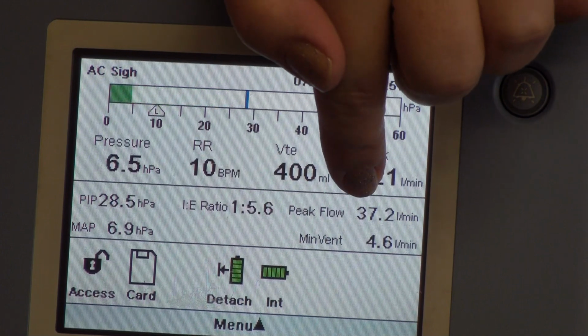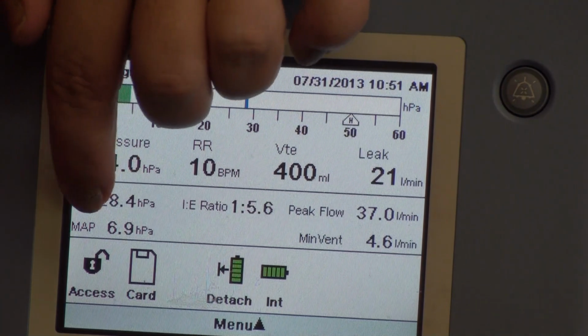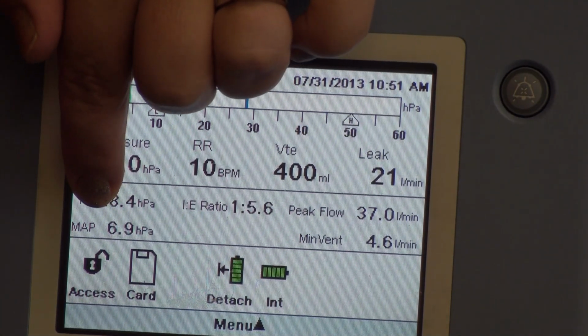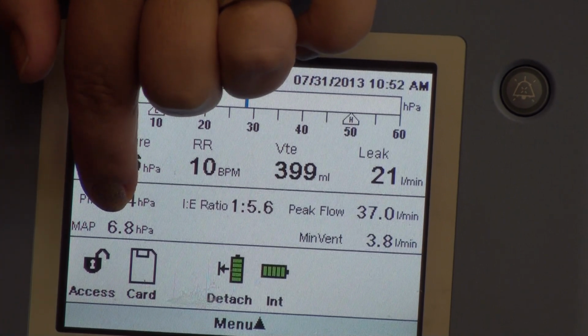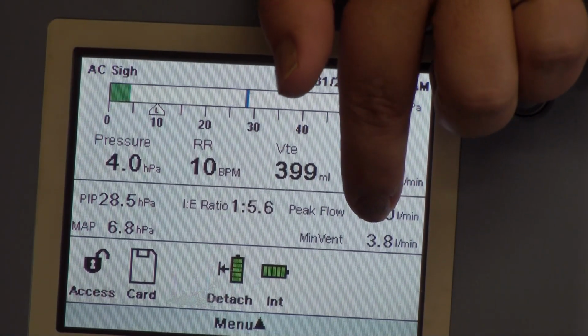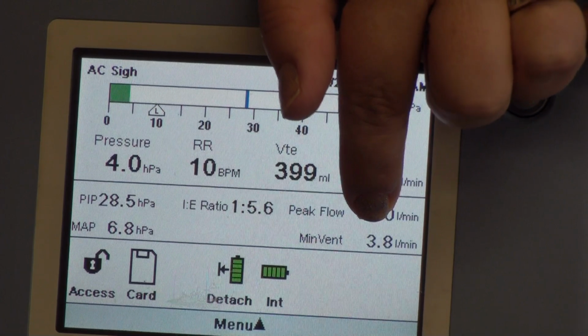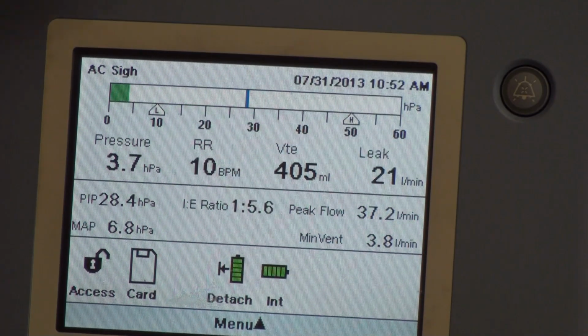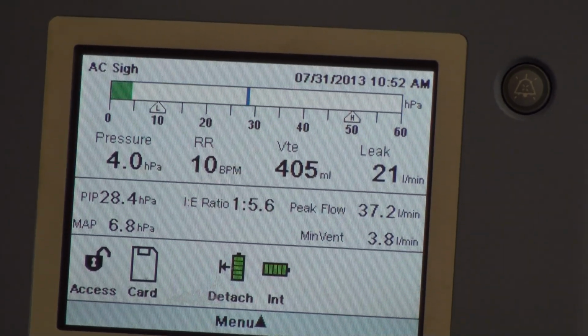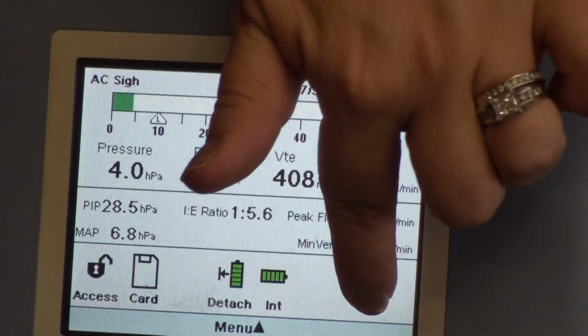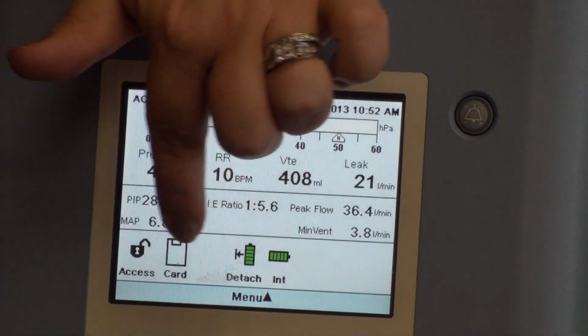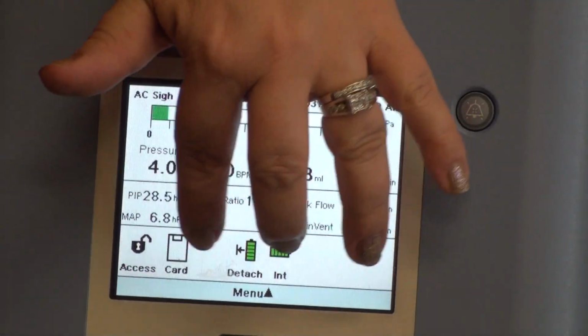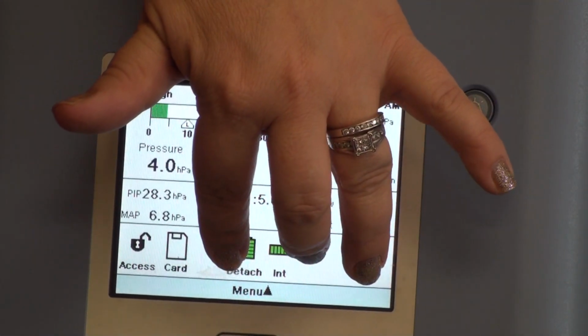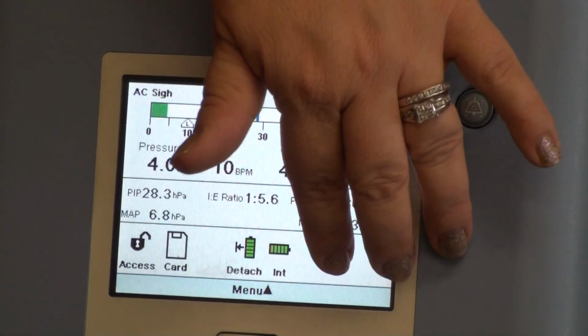I had 37.2 in that one. My mean airway pressure is down here. That's just my average of my airway pressure. And then over here, I'm going to have my minute ventilation, which right now is at 3.8. The next section is going to be my status panel, which is this down here, okay? And on yours, you're going to have every single possible light that can possibly be lit up in this one. Mine, I don't have that because the ventilator is running.